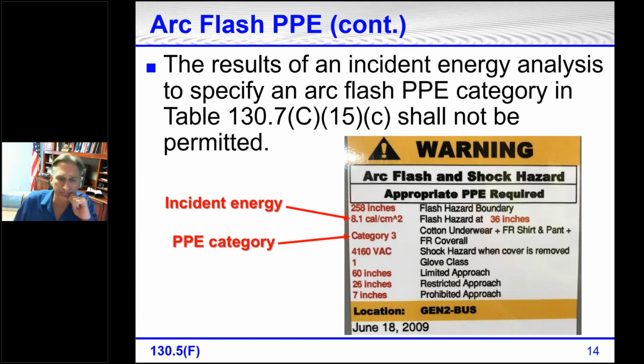Here's a label that I took a picture of a couple of years ago. This label was on a piece of 4160 volt equipment, 4,160 volts, as you see on the label. It was done quite a while back. Of course, even when I took the picture, it was out of date, right? We know that it's required to review the label every 5 years, and this label has 2 things on it. It has the arc flash boundary, which is required to be there, but it has incident energy at the working distance, and it also has the category.